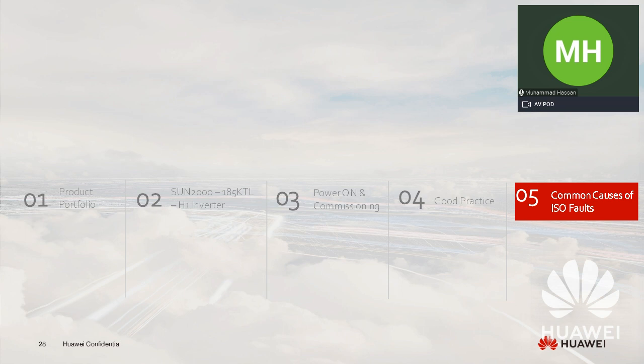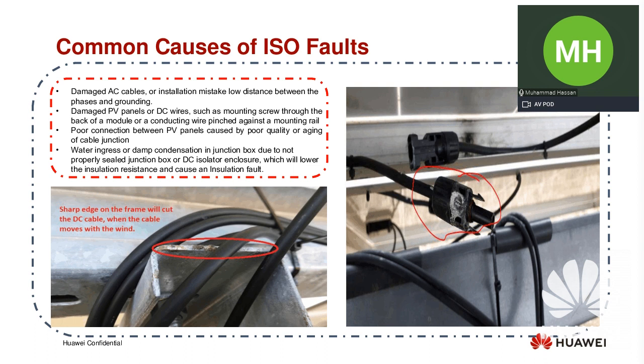Some common causes of ISO fault. I have seen many sites where ISO faults appear for the inverter, not on the 185 KTL, but on all the other inverters as well. So I would like to show you some pictures. These are small things which customers are not focusing on, and then they start creating problems and it ends up in a big loss. So it's always recommended that whenever you go to a site, you oversee things, and if you find something, fix the problem as soon as possible to avoid any damage in the future.